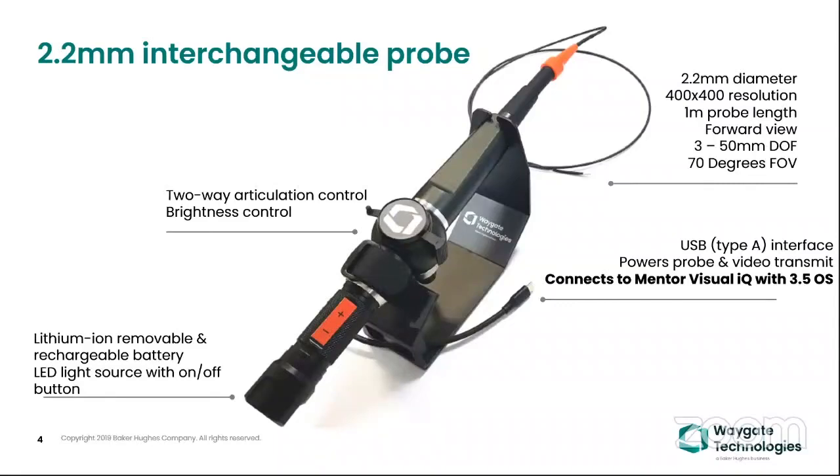You can have all your video or images recorded on the MViQ platform, and all image management features like contrast, image super-imposition, and text annotation — those functions you can utilize using the MViQ platform. This is on a CMOS imager with 400x400 resolution, a depth of field of 3 to 50 millimeters, and a 70-degree field of view.